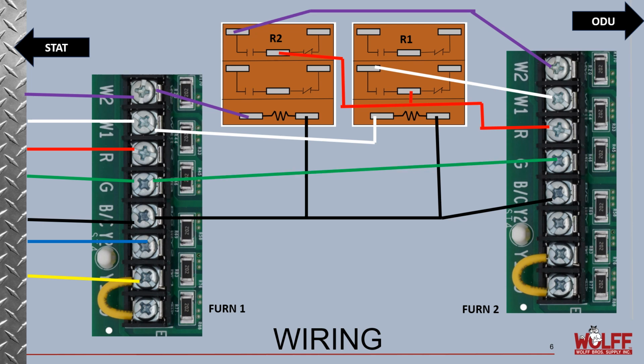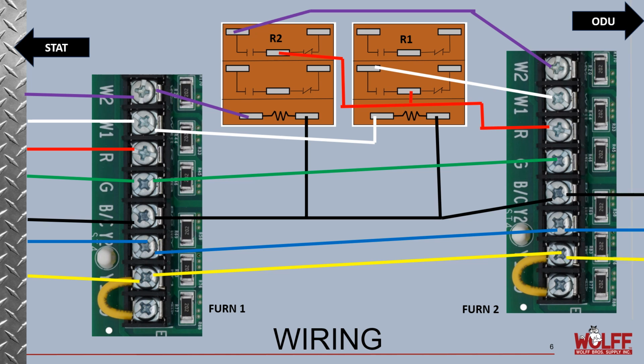Next, we're going to basically wire G from furnace 1 straight to G on furnace 2. And we're going to wire Y2 from furnace 1 straight through to furnace 2, and Y1 from furnace 1 straight through to Y1 on furnace 2. Then we're going to take common, Y1 and Y2 out to the outdoor unit. This basically completes your low voltage wiring for your twinning setup.